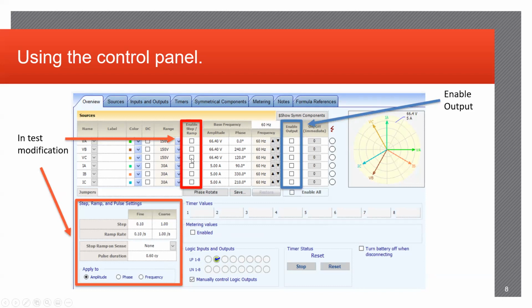This section up here, as shown as well, will actually allow you to enable the step or ramp change to either one or multiple sources during testing, which again is extremely useful if you want to just manipulate one phase at a time or one value at a time. And then the last section, again, before you freak out and wonder why your relay is not getting any voltage or current readings, always check to make sure that your outputs are enabled, and make sure that you allow the current or voltage to be injected into the relay.